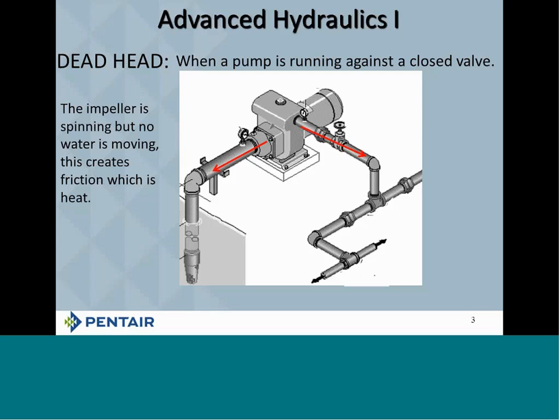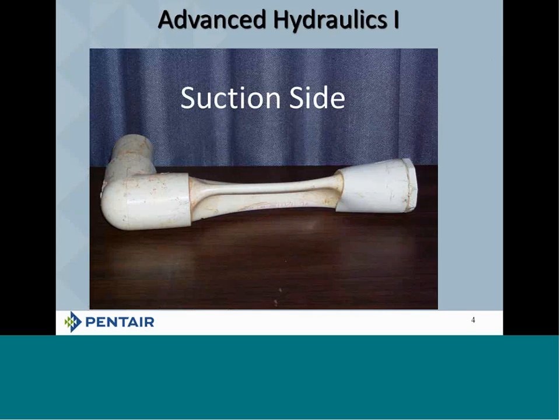So on the suction side, when you get a lot of heat, if you're using a plastic pipe, and here's the big word, if you're using a plastic pipe, this is what's going to happen. You can see there that that plastic pipe just absolutely collapsed.